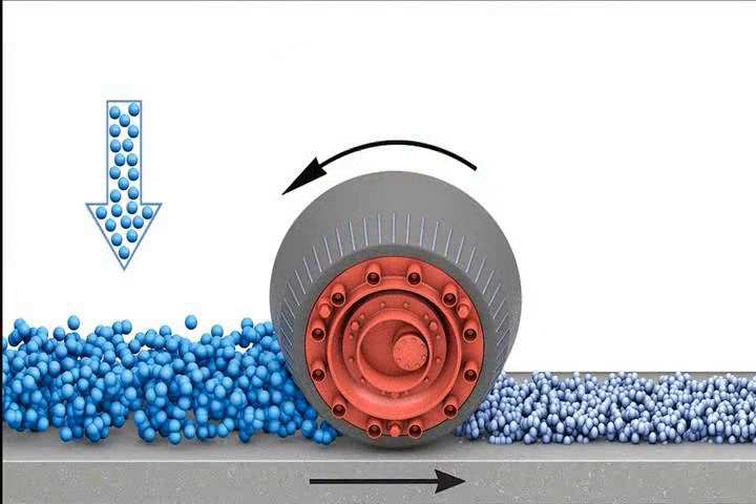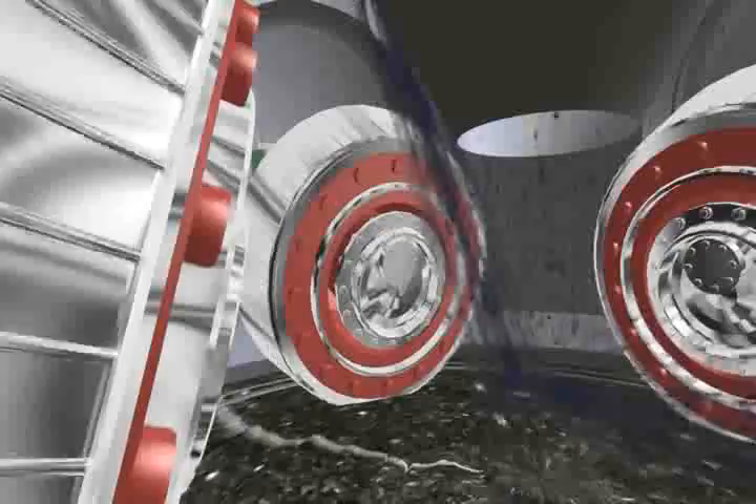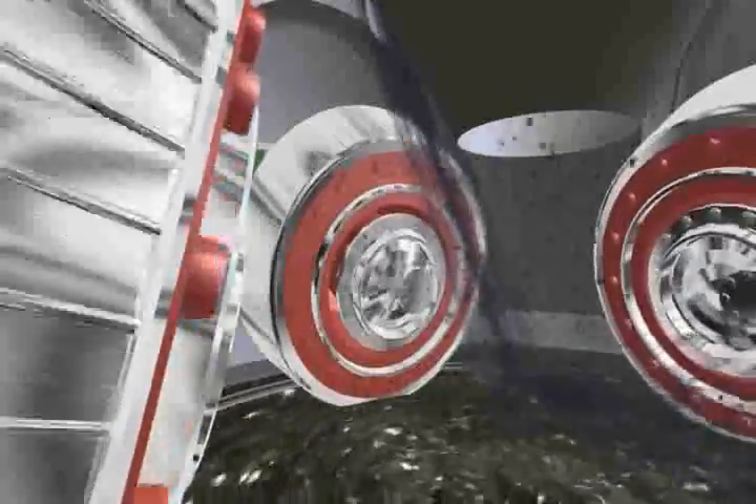The grinding material is comminuted in the Loesche roller grinding mill between the rotating horizontal grinding track and the fixed grinding rollers. Grinding is affected primarily by the force of pressure with a small amount of shear force. This effect is created by tapered rollers whose axes are angled at 15 degrees with respect to the horizontal grinding track. Comparative investigations conducted during the 1930s showed that this is the best way of achieving optimum comminution with minimum wear.